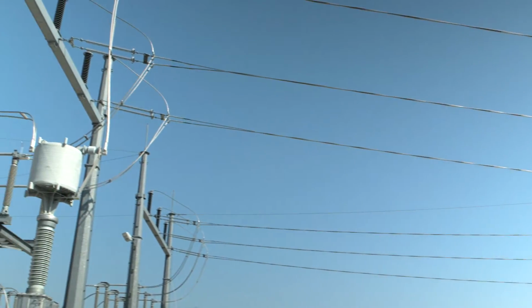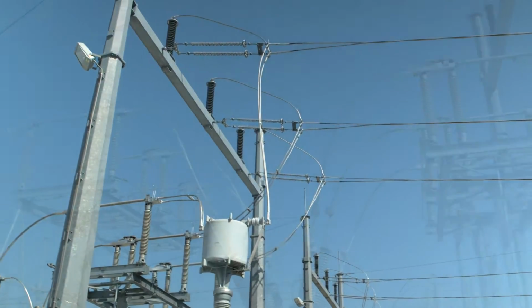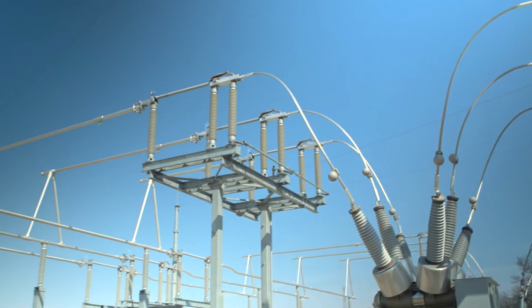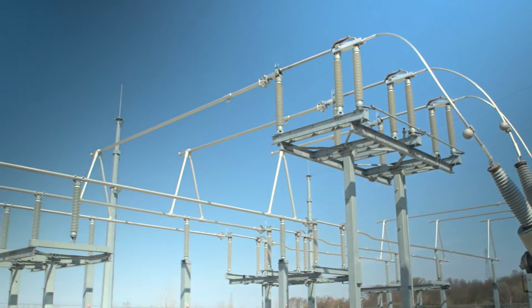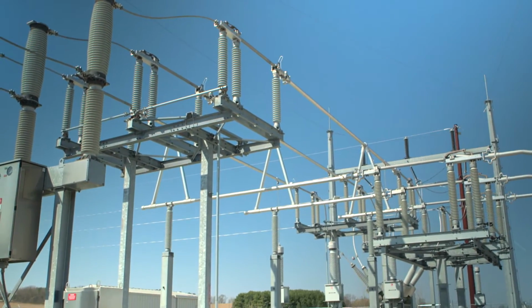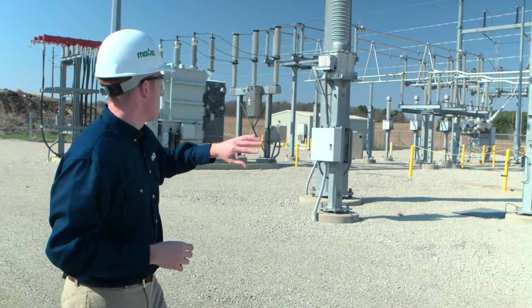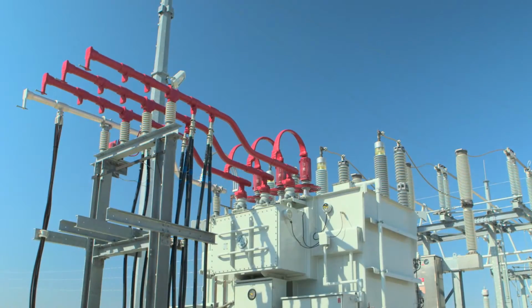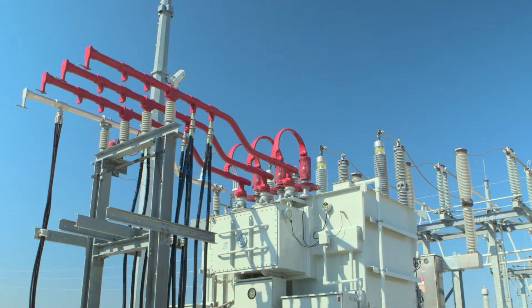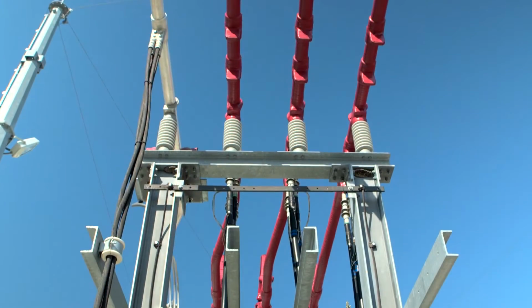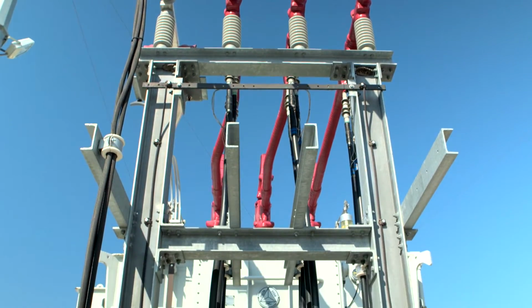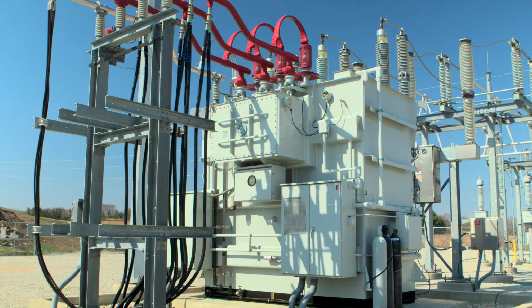This substation has three 138,000 volt transmission lines coming into the sub. The transmission line would enter here, go through the set of disconnect switches, through the circuit breaker, and from the breaker it'll go to the buswork. The purpose of the buswork is to distribute the power to the various components of the substation, and some of the power will also feed to our transformer. This transformer steps 138,000 volts down to 14,000 volts, and you need to do that so you can safely transmit the power to our customers outside of the substation.